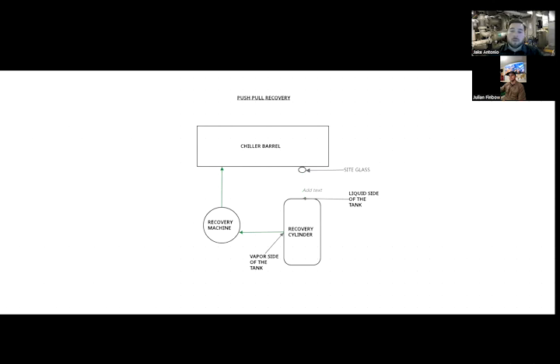So what you would do is you would close off that valve. Now the liquid's all in the tank, and you would actually reverse these arrows, and you're going to be pulling out vapor now using your recovery machine. So now at this point here, your liquid line's closed off to the chiller. All the liquid is out of the chiller and it's back into the recovery cylinder here. And now we're going to get the vapor out of the system and pull the vapor out of the chiller through the recovery machine and into the recovery cylinder. And then once all the pressure in the chiller is out and it's in the recovery cylinder, then the recovery is complete. So that's kind of a basic introduction to the push-pull method on recovering refrigerant out of a chiller.